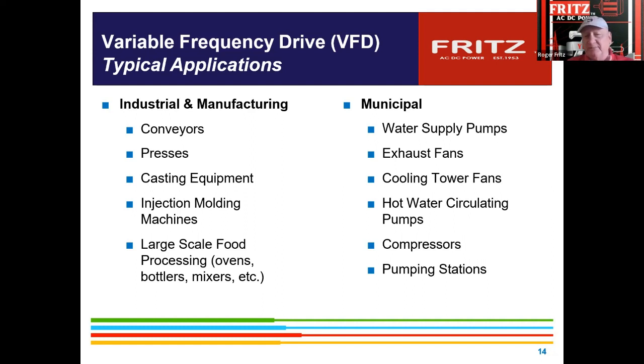Been involved a lot in municipal business, water supply pumps. There's a lot of what they call Parco valves that are put in front of them to eliminate water hammer. When you put a drive control on, you can take that valve out and get rid of those losses going across that head. Plus, you're able to stabilize the pressure and voltage, so you don't have to have pressure regulation valves.